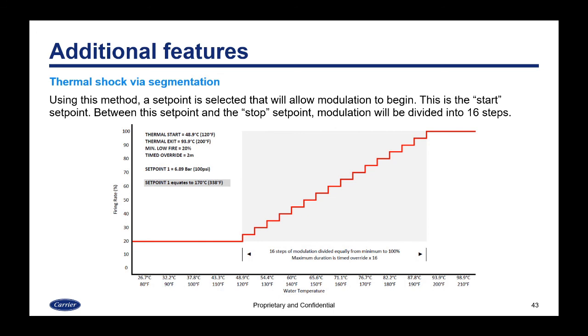The next method is via segmentation. In this method, a set point is selected that will allow modulation to begin, which is the start set point. Between that set point and the stop set point, it's divided into 16 steps of modulation. And you can see it'll step up gradually. You can set time limits for each step. So if your time limit is exceeded, it'll move to the next step. Or if the temperature threshold is reached first, it will move to the next step.